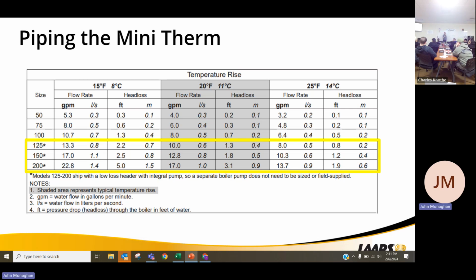Again, those ones come with the low loss header on there to ensure proper flow through the heat exchanger. Again, if you don't have proper flow through that heat exchanger, you risk sooting it up. You risk rupturing it, where you're going to get hot spots in it.